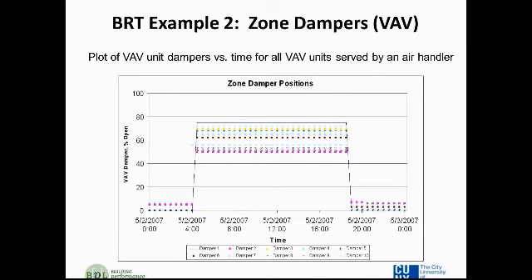The damper remains closed when the building is not occupied. It remains closed during building warm-up. So this is obviously good operation. So you save all that energy that you would have otherwise thrown away if, in fact, you have the outdoor air damper position open. And by the way, if the fan were on at those unoccupied hours, then you'd really be losing a lot of energy. Okay, going on to another example.